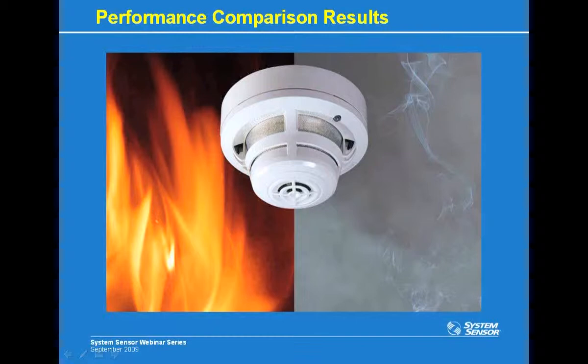They can introduce smoke, heat, and carbon monoxide either individually, sequentially, or you can introduce multiple products at the same time. So you could introduce carbon monoxide and heat and smoke all at the same time within that confined chamber, and that would be a way to test that it is responding quickly to a combination of inputs. Again, this isn't meant to be an advertisement for SDI, but they have developed that device specifically for these next generation multi-criteria detectors that are starting to come onto the market.